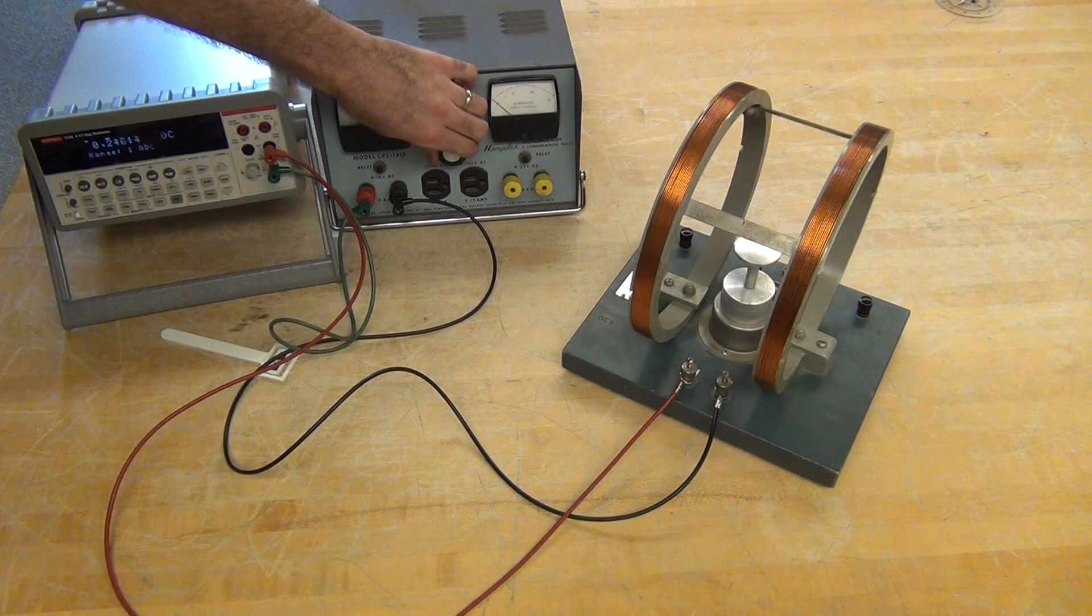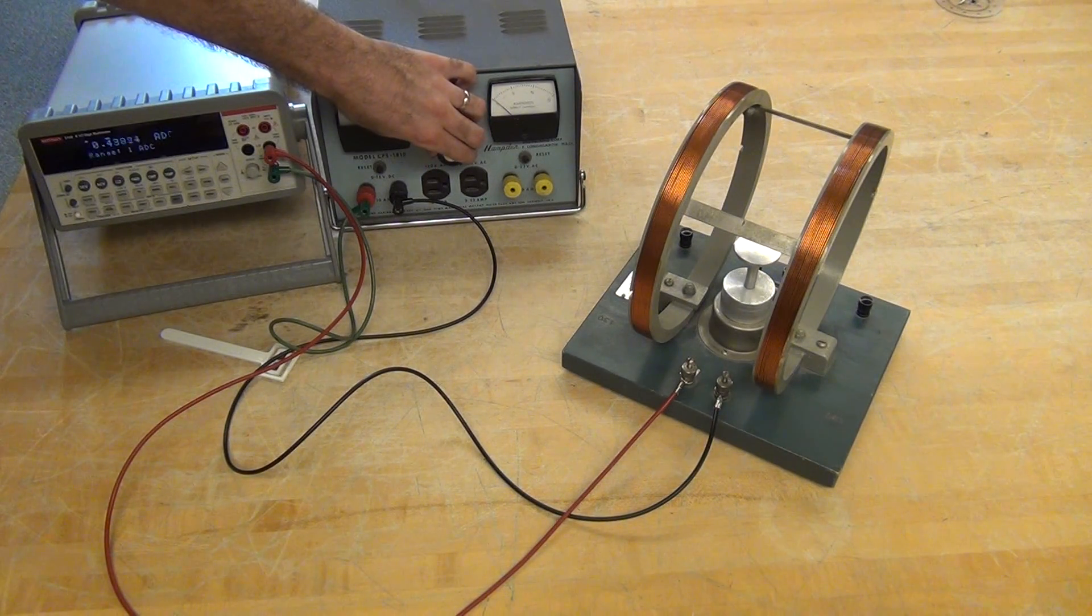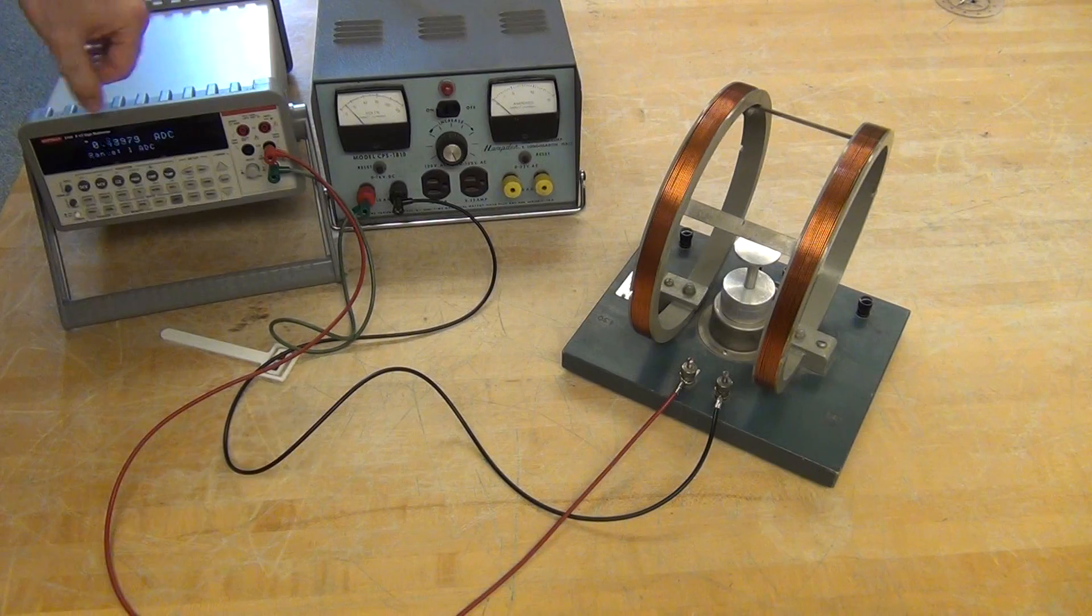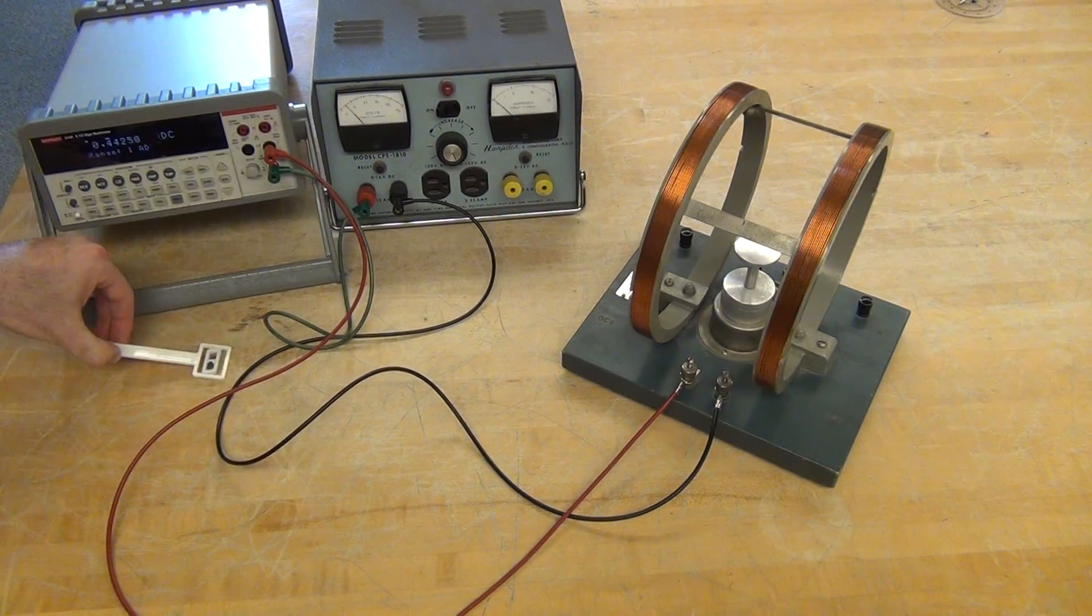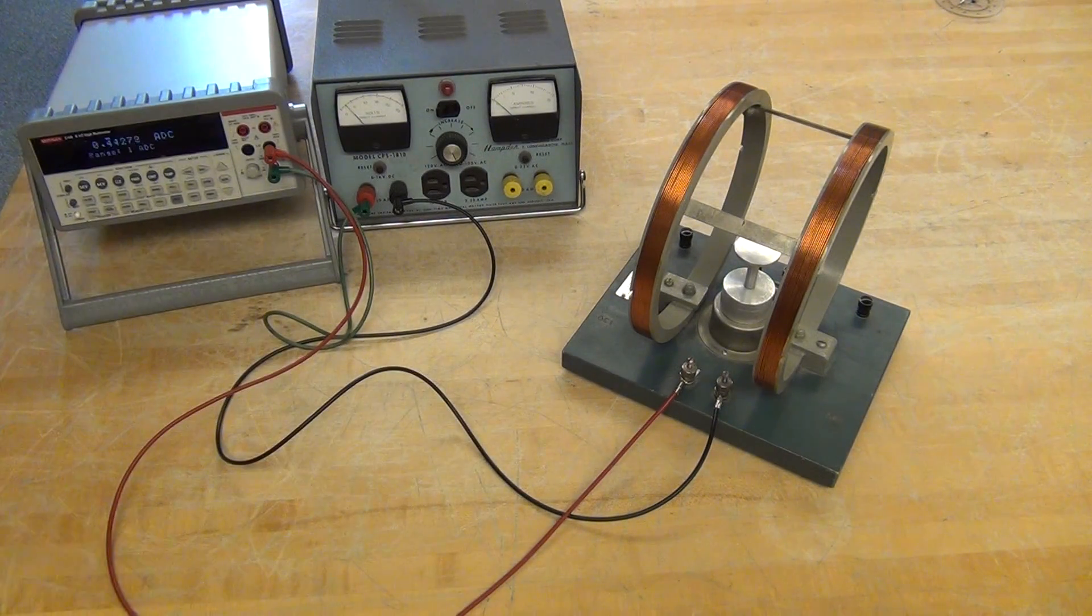Go to one amp DC maximum range until we have 0.4, 0.5, about half an amp running through our coil.